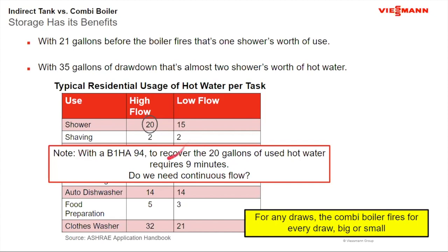shower. With this kind of performance here, you take a shower, and if I use 20 gallons and that boiler came on, by the time the next shower started, I'm back up to 40 gallons of usable hot water. So when I start to look at a combi boiler versus an indirect water heater, the storage, which a lot of times is presented as a negative, actually is a very big positive when you look at the way that we use hot water, okay?